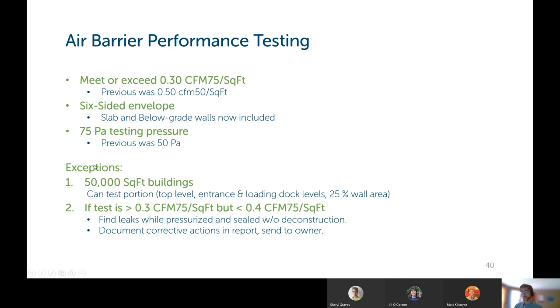There's a couple exceptions to this. If you've got a large building, 50,000 square feet or more, you don't need to test the entire building. You can test a portion of the building, but you must do the top level that is underneath the roof, any entrances or any level that has entrance and loading docks, and you must test about 25% of the wall area and pass those requirements.